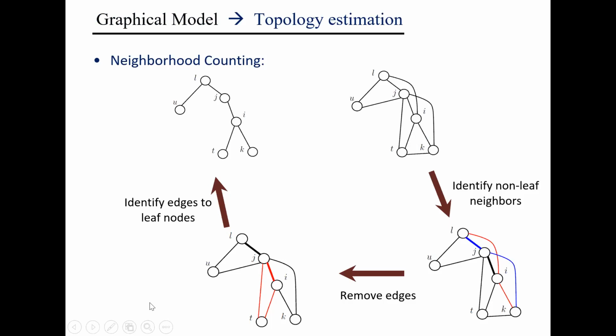So this is another rule which says that in this kind of a tree-like topology, every neighbor of a leaf node should also be a neighbor of its true parent. So you can use that to identify what the true parent is. And since now you have learned the edges between internal nodes and the edges between leaf and their parent, you have more or less established conditions under which you can estimate the true topology. Okay. And what I showed was for radial grids.